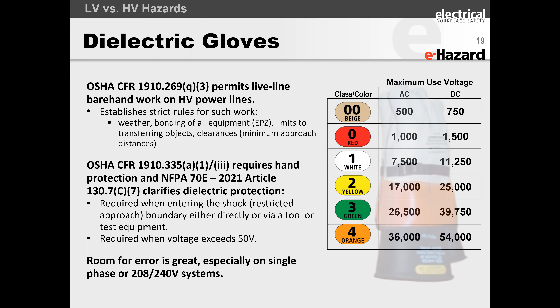So there's great room for error, especially when people think about 208 volts or 240 volts, because people may believe that, hey, I work on the system in my house all the time. I'm not using a glove. Why do I need a glove now when I'm in a factory? Okay. And at low voltage, you always need that glove. There's very few exceptions in low voltage where you do not need the glove.